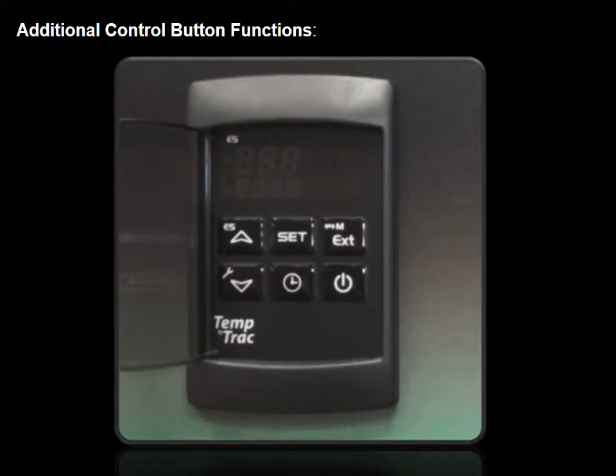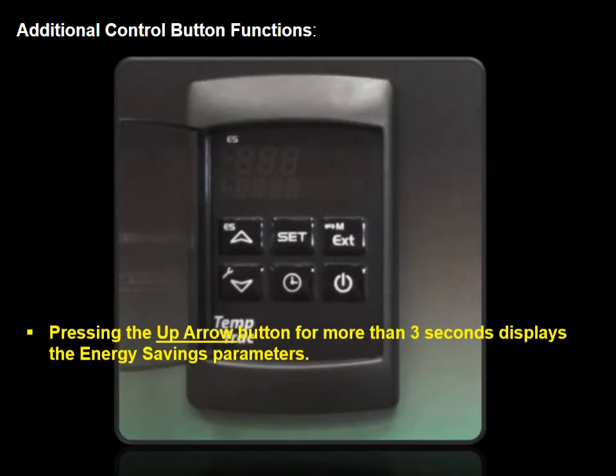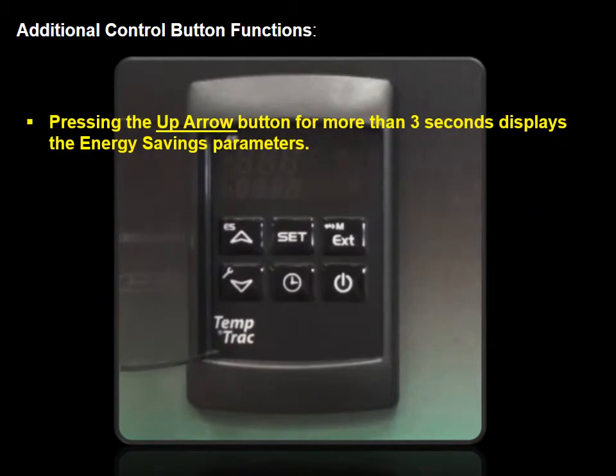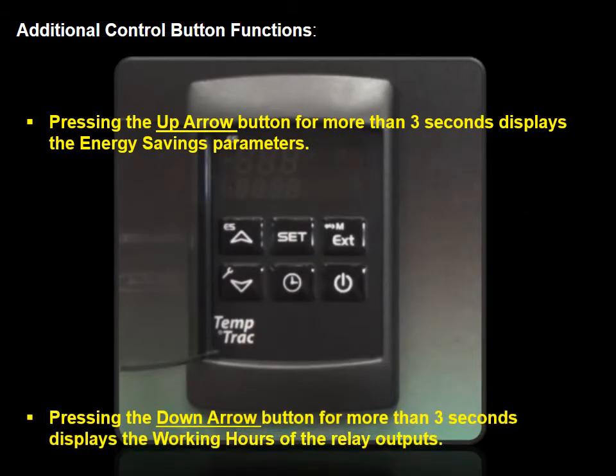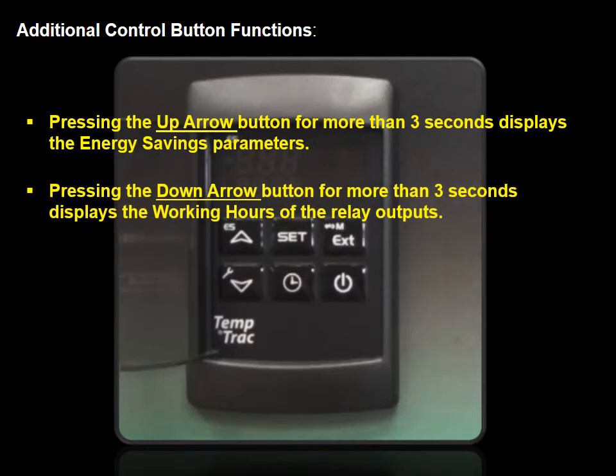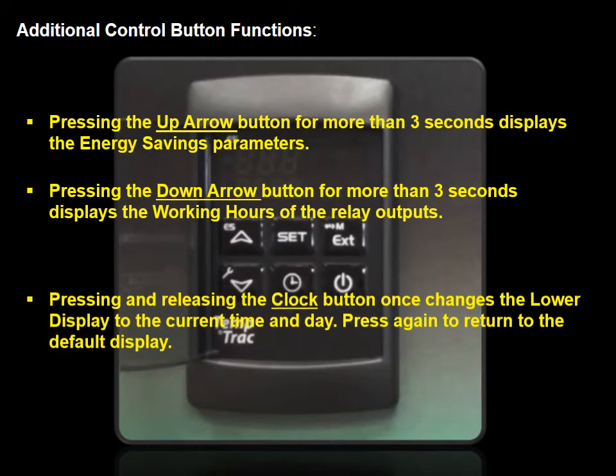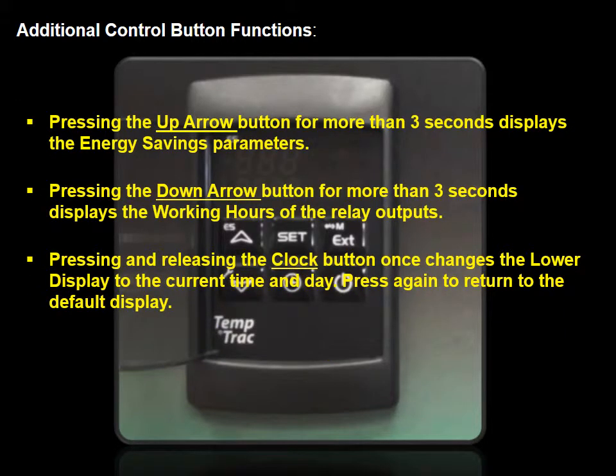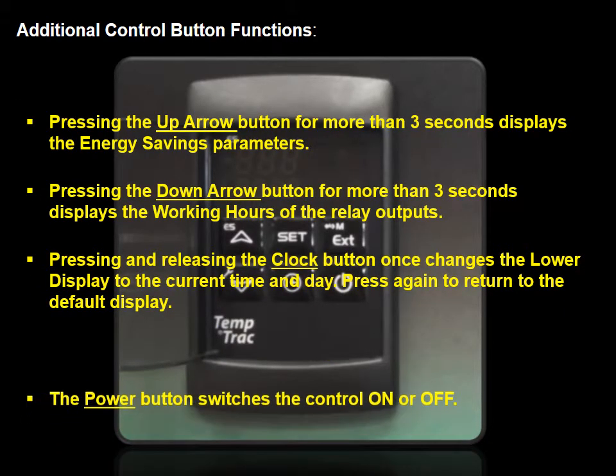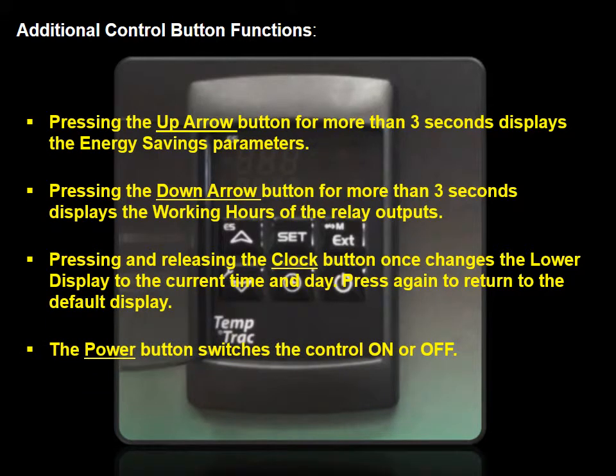Press the button again to return to the home screen. Pressing the Up arrow button for more than 3 seconds displays the energy savings parameters. Pressing the Down arrow button for more than 3 seconds displays the working hours of the relay outputs. Pressing and releasing the Clock button once changes the lower display to the current time and day. Press again to return to the default display. The Power button switches the control on or off. The Temptrac User's Manual will provide additional information on how to change or adjust these parameters.